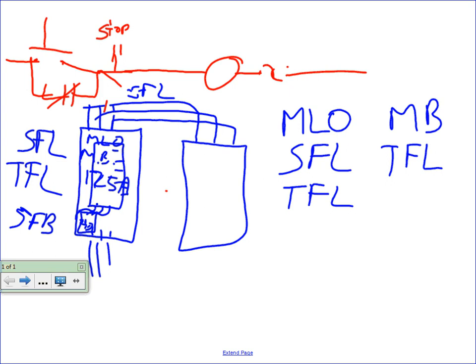Okay. And there are cutoffs, and again, call me, because on a 250 amp or smaller, we can put 1 sub-feed in. On 400 amps or bigger, we can put 2 in. And it all has to do with the lugs for the feed-through, right? Because at 400 amps, those feed-through lugs are rated for 2 cables per phase. So now we can sub-feed 2, whereas at 250 amp, those lugs are only rated for a single cable, and that's why we can only do 1.